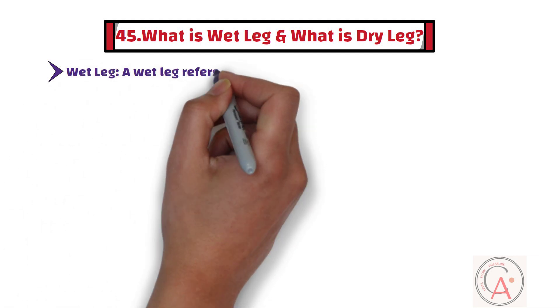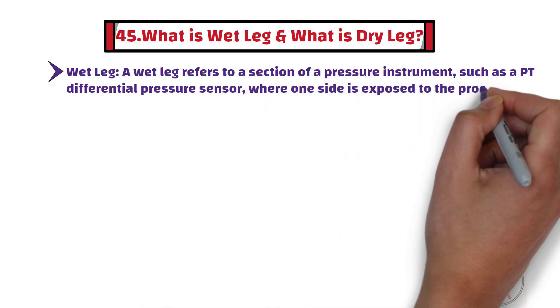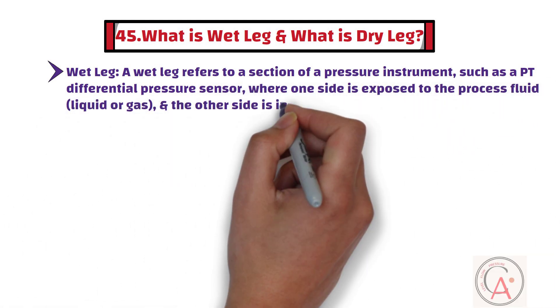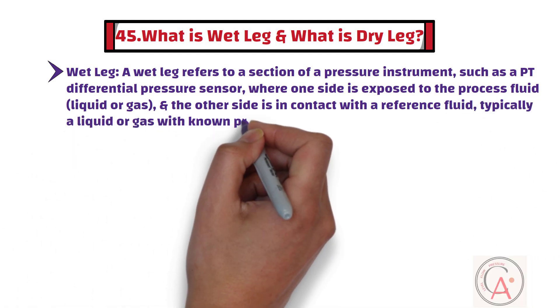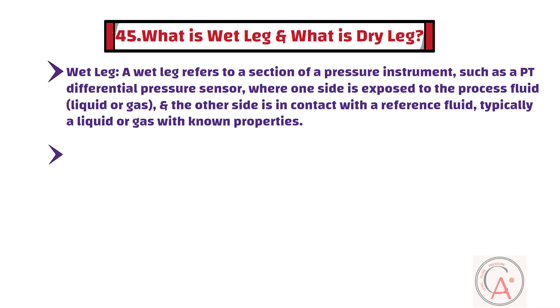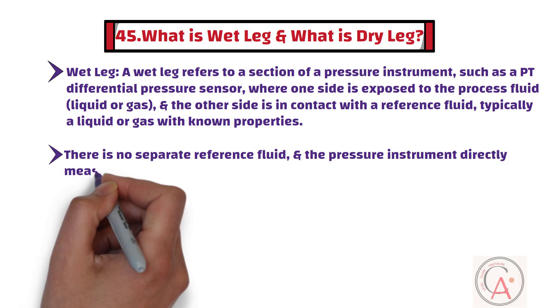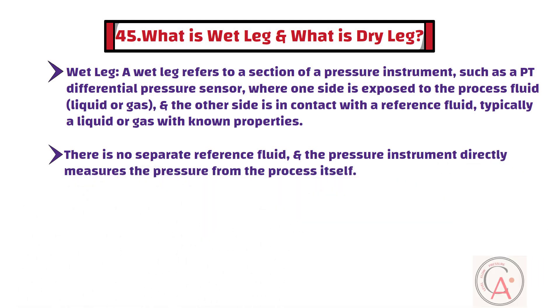Question 45: What is a wet leg and what is a dry leg? A wet leg refers to a section of a pressure instrument — such as a pressure transmitter or differential pressure sensor — where one side is exposed to the process fluid and the other side is in contact with a reference fluid, typically a liquid or gas with known properties. In a dry leg setup, there is no separate reference fluid, and the pressure instrument directly measures the pressure from the process itself. Dry leg configurations are commonly used where it is not practical or necessary to use a separate reference fluid.